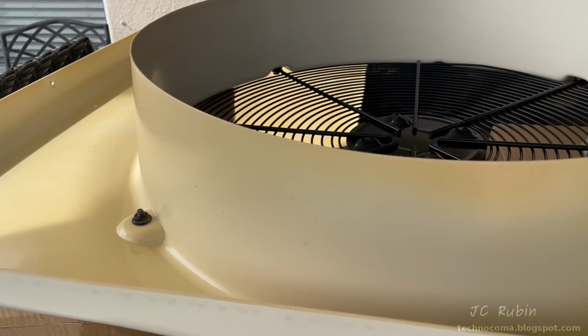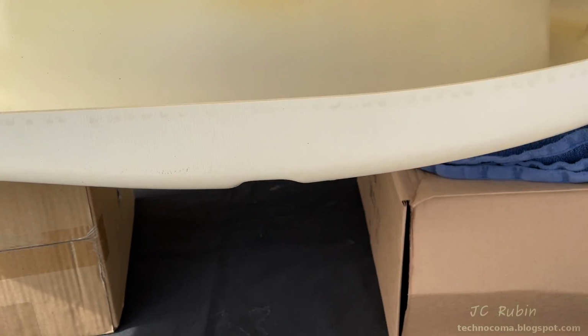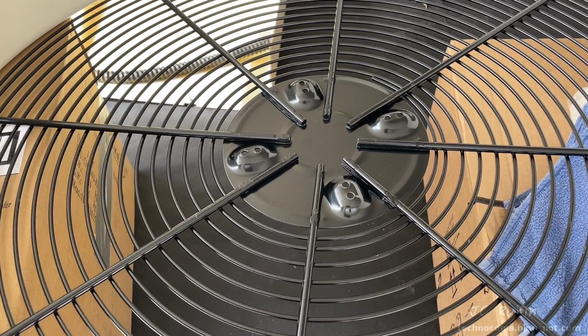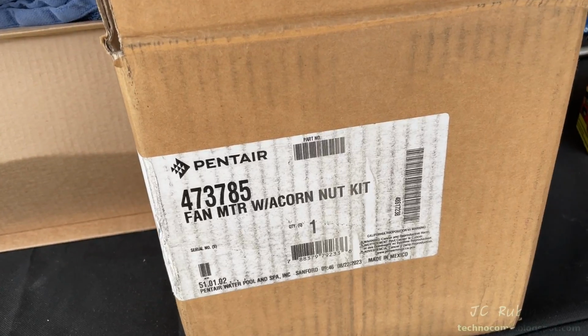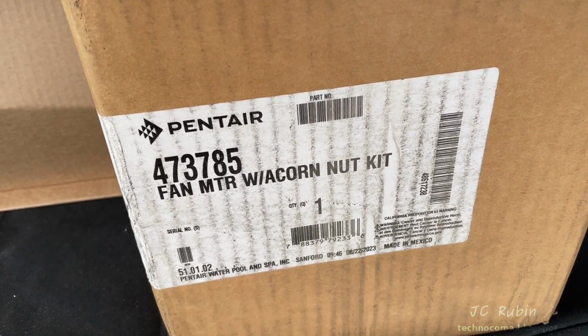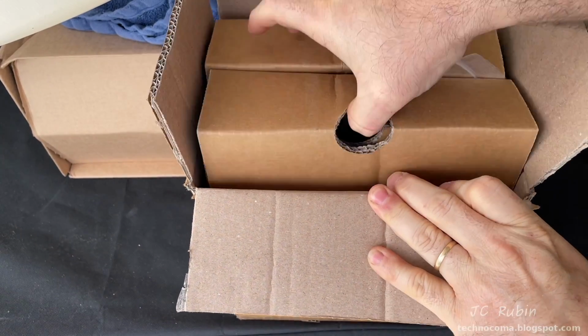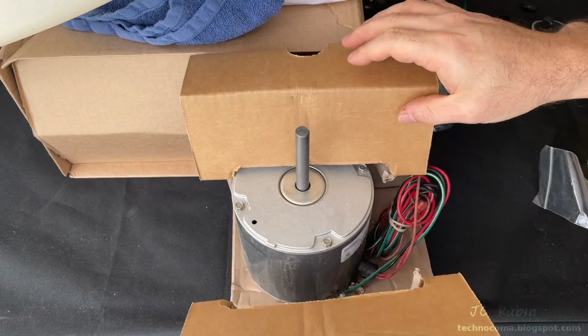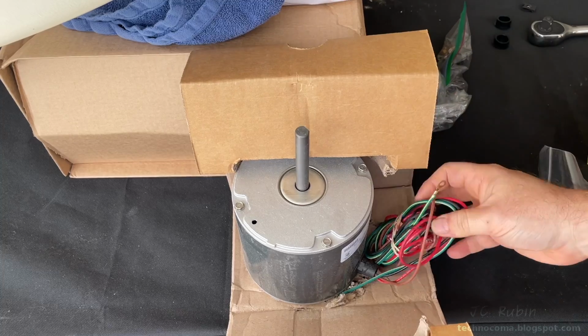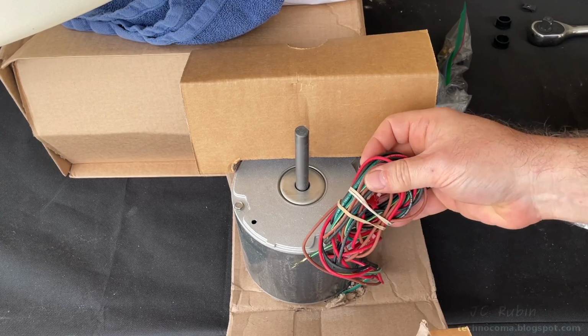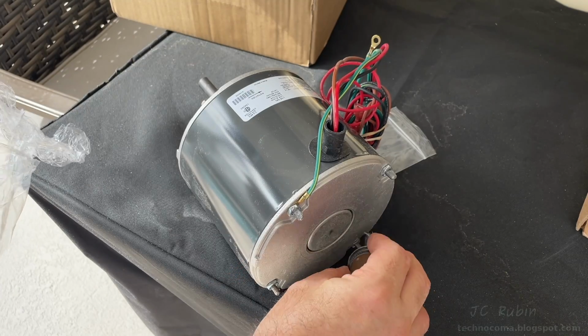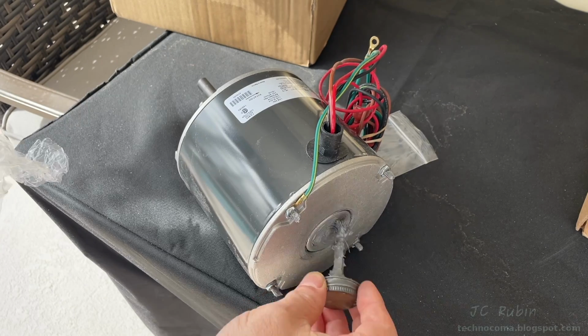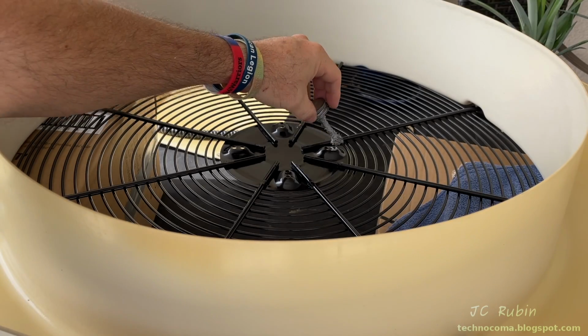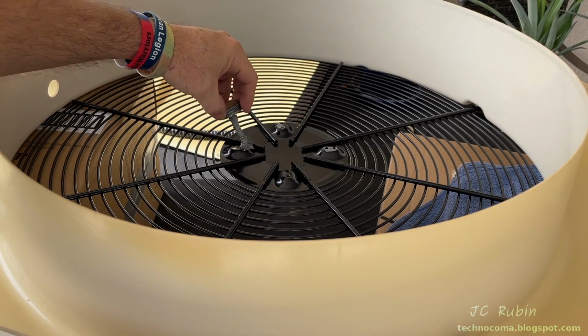Meanwhile, the top is supported on two cardboard boxes so we could do the motor and fan installation from both sides. The motor and acorn kit is from Pentair, 473785, and it seems in every way identical to the old motor, with the electrical wires as well as the ground. Anti-seize is added to the threads and the area in the middle that rusted out last time. It's also added to the mating surface on the bottom of the grill.